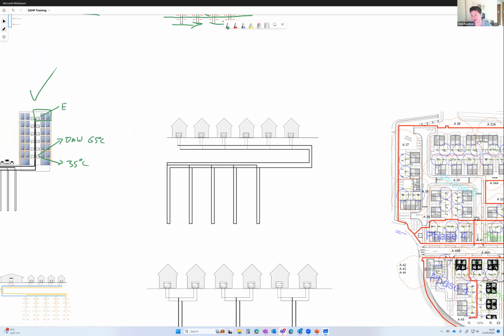Heat pumps are very robust bits of kit - they're fridges, and fridges last a long time. They're very robust because they've got very few moving parts, and those tend to be hermetically sealed inside a gas cycle with lubricants. So it's a long-living piece of equipment. What can cause failures? Bad controls - that's probably the most typical problem. Short cycling, starting and stopping repeatedly, can cause issues. Distribution system problems can also knock on into heat pump problems. But natively, they are incredibly robust and reliable bits of kit.